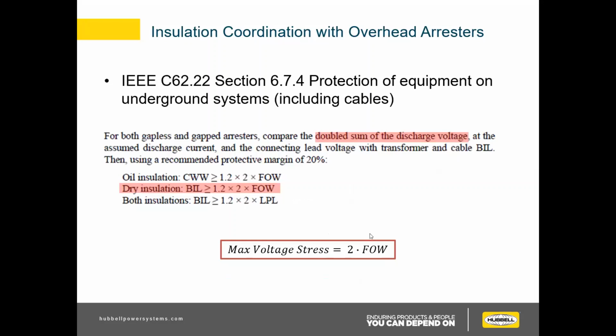So this is the IEEE C62.22 standard, which kind of summarizes this. We need to compare the doubled sum of discharge voltage. In the case we just talked about, it's 35 kV doubled to 70. You need to assume discharge current and the connecting lead voltage with transformer and cable BIL. It's recommended to have a protective margin of at least 20%. That's what IEEE recommends. For this case, dry insulation means cable insulation.